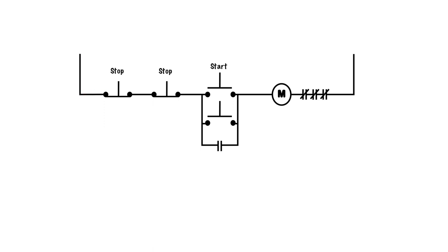Anything that starts a circuit needs to be in parallel. So if I press this down, it will energize M, or if I press this down, it will energize M. Let's take a look at what happens when we start energizing or pushing down on our pushbuttons.